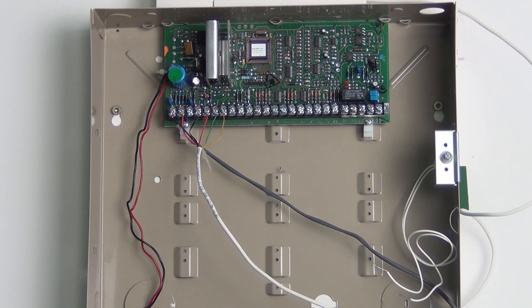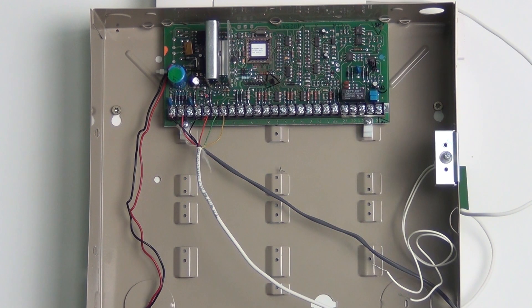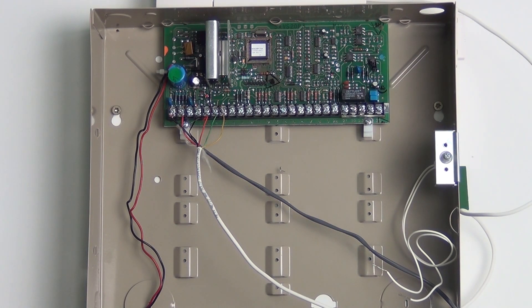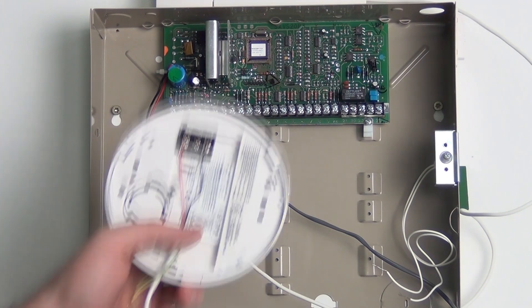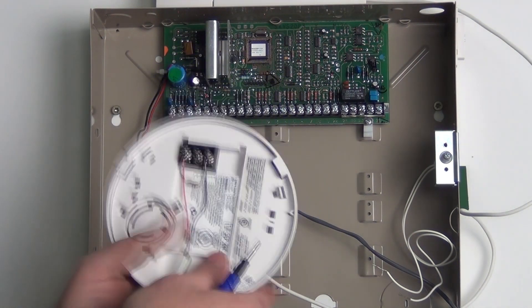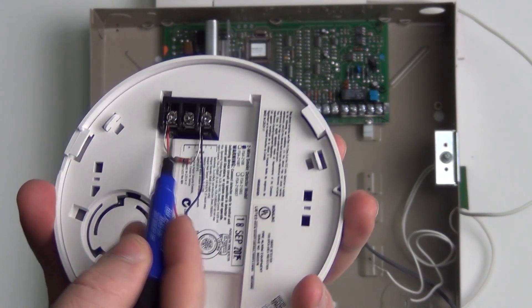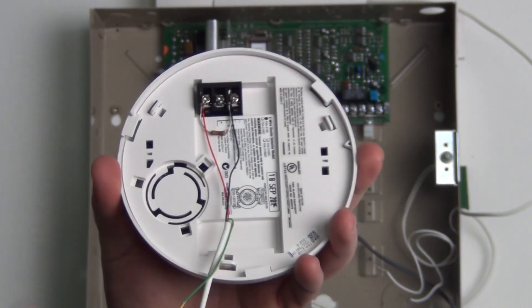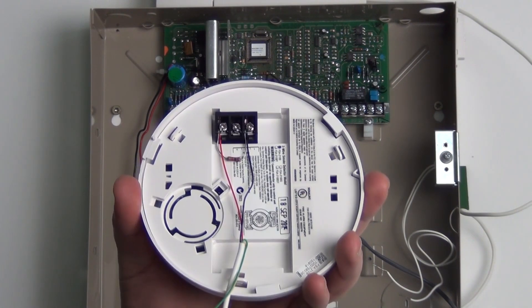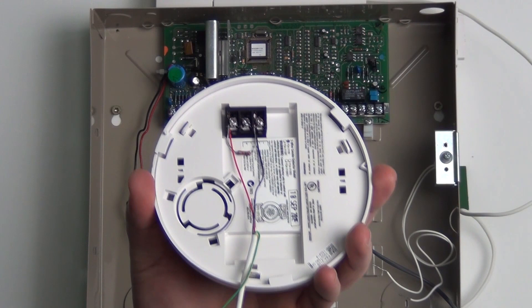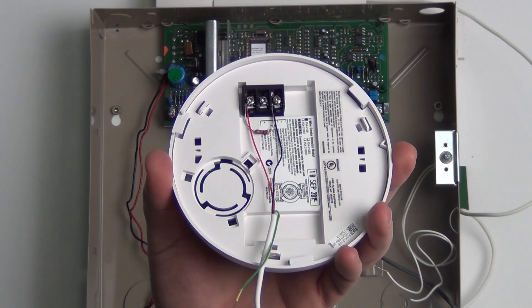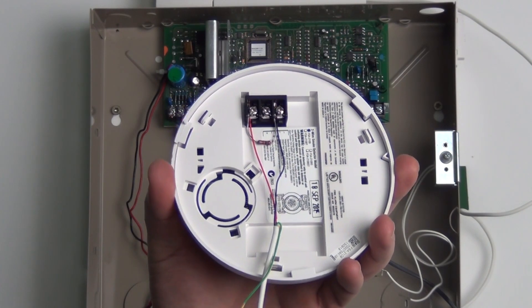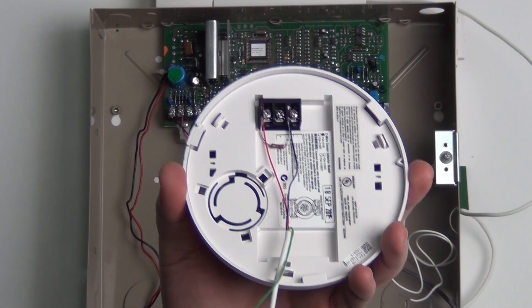The first thing I'm going to wire into this system will be a 2-wire smoke. 2-wire smokes always go on zone 1 on a Honeywell Vista panel. If you have more than one 2-wire smoke, you're just going to run all these together on zone 1. They cannot be zoned out individually. As you see here, I have a 2-wire smoke and I have placed the resistor at the device across the 2 terminals. You will do this with your resistors—they go at the item itself instead of in the panel. If you want a deeper explanation about resistors and how you use them, check out Jason's video. I'm going to put a link at the bottom of the screen. I'm not going to go in depth on resistors since he already did, so check his video out for more information.